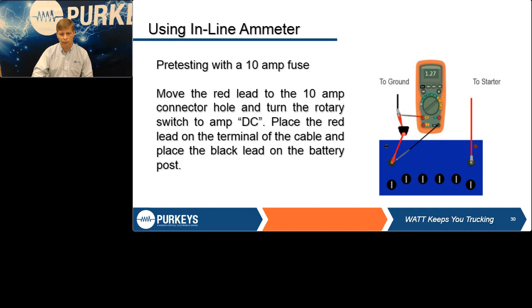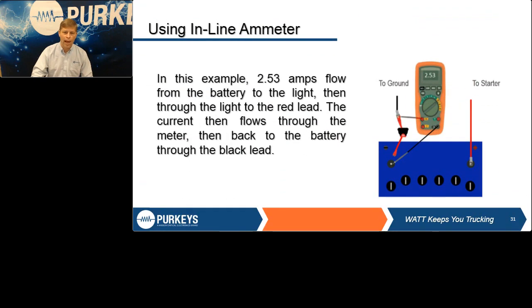You're actually kind of cheating, since we gave you the answer on the screen. You're going to actually only see about half that current. The reason is half the current's going to flow through the fuse holder and half is going to go through your meter. So once you make that connection, you want to pull that fuse holder out. Now all that current has to go through your meter so you get a very accurate reading. Just like we were saying before, if you've forgotten and left one ground cable on, all that current is not going to flow through your meter, so you're not going to get an accurate reading.